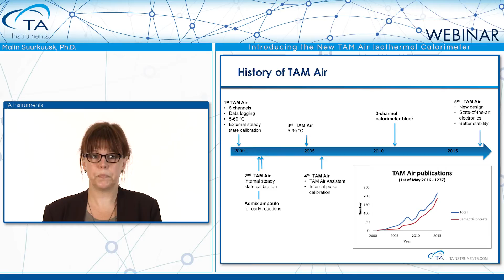So if we look at the calorimeter itself, it consists of a thermostat and a calorimeter. It's an air-based thermostat, so flowing air will control the calorimeter temperature and will minimize the outside temperature disturbances that will come from the laboratory environment. All the calorimeters are held together in a single removable block, either with 8 or 3 individual calorimeter channels, and these blocks are user interchangeable inside the thermostat. Each calorimeter is a twin heat flow calorimeter, and we have both the sample and a reference side for the measurement of the heat flow. I will show the calorimeter parts in detail.